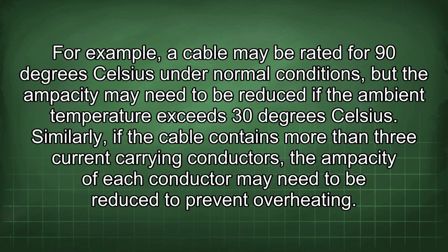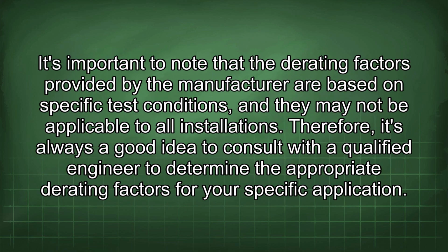Similarly, if the cable contains more than 3 current carrying conductors, the ampacity of each conductor may need to be reduced to prevent overheating. It's important to note that the derating factors provided by the manufacturer are based on specific test conditions, and they may not be applicable to all installations. Therefore, it's always a good idea to consult with a qualified engineer to determine the appropriate derating factors for your specific application.